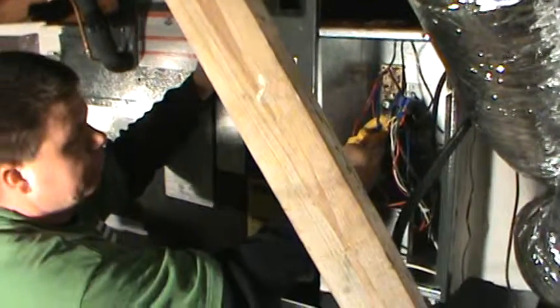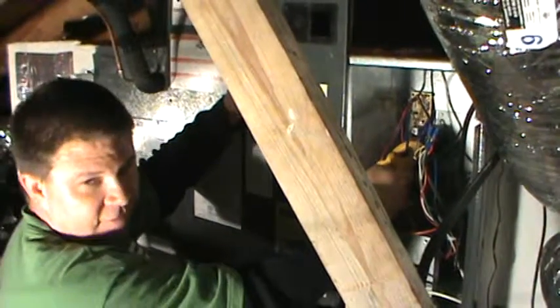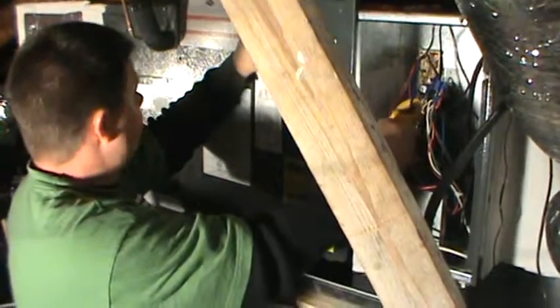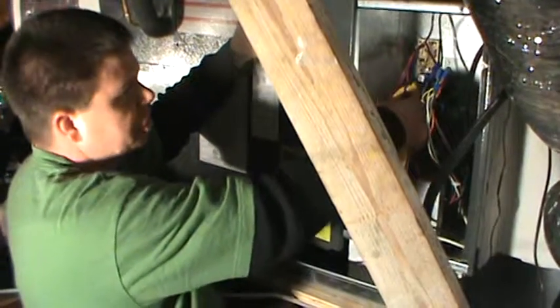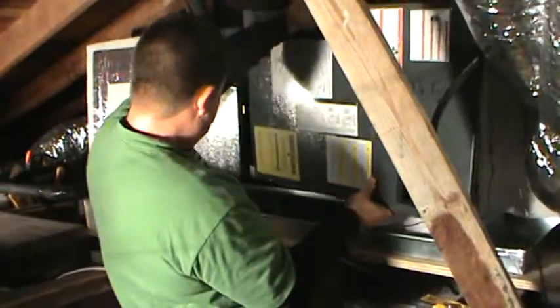So checking, we got 1.5 amps, so definitely running below its rated amperage, so we're in good shape there. Go ahead and shut the unit back down. Put the panel back on.